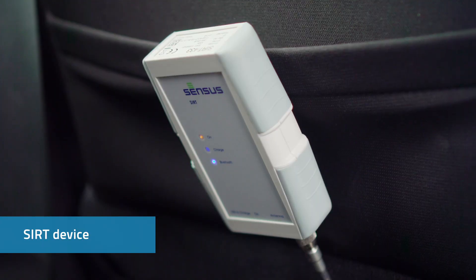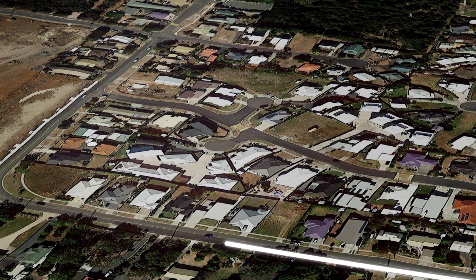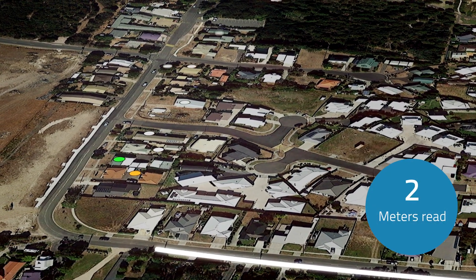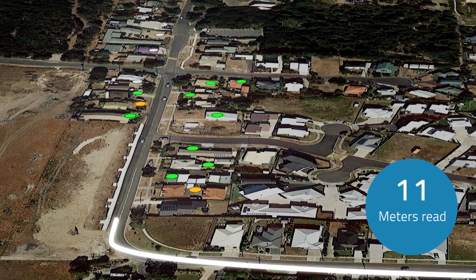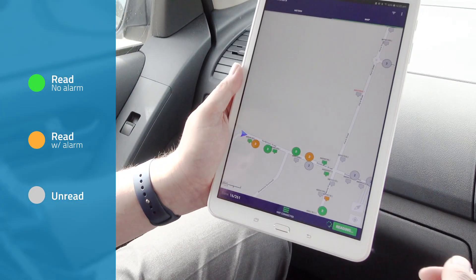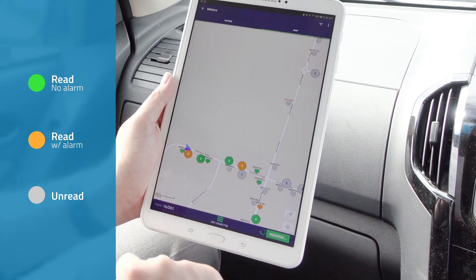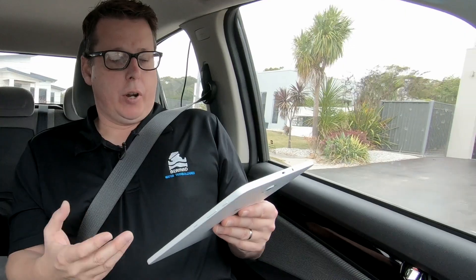We'll go ahead and run the route. First of all, we've connected our SIRT device — that's the radio receiver. Click 'Read All' and you can see straight away we're starting to pick up some meters. We've already picked up 8 of 261. Green represents that the meter has been read with no alarms, orange means there is an alarm, and grey means it hasn't been read yet.